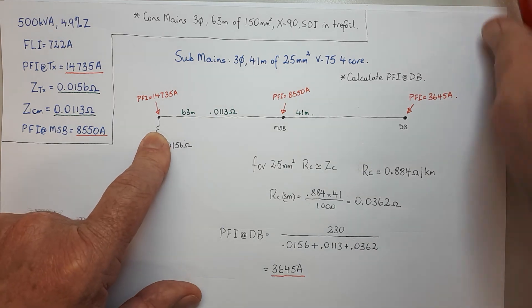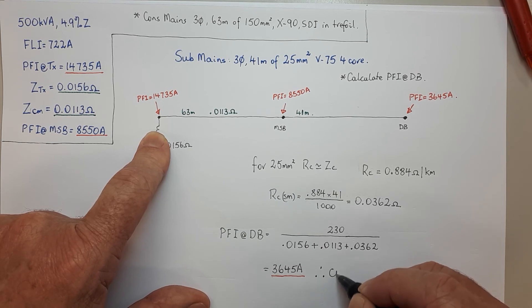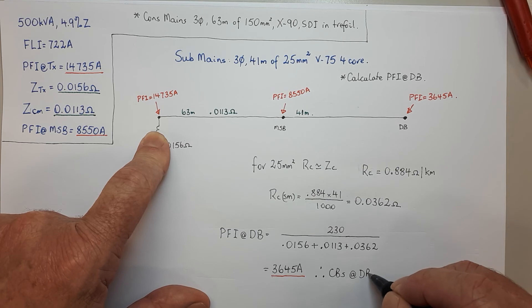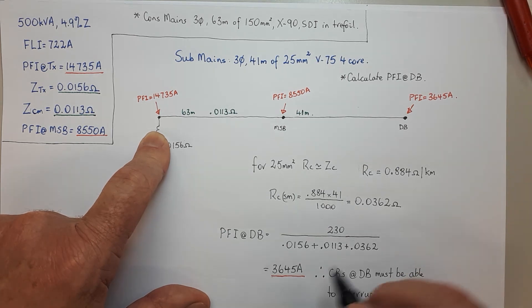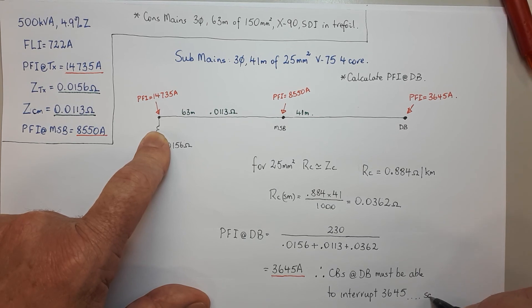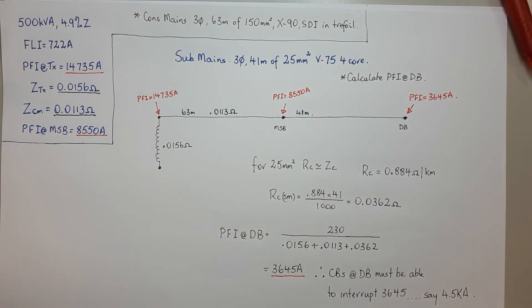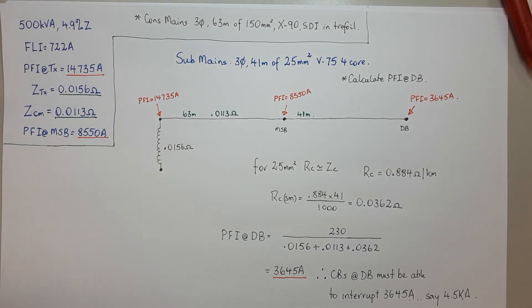Therefore, circuit breakers at the DB must be able to interrupt 3,645 amps, so you'd be looking at say 4.5kA or whatever you pick — it just has to be more than 3,645 amps. And that gets us there, that's everything.